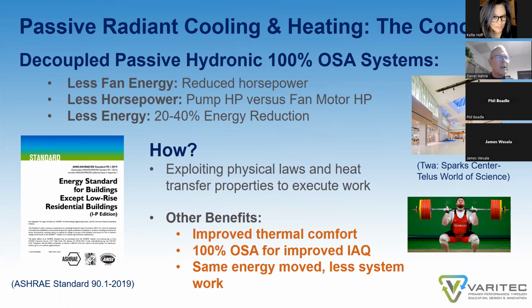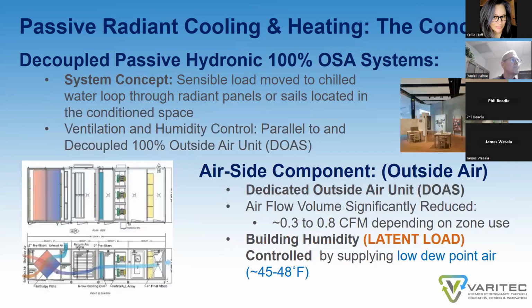There are other benefits other than the energy component as well. There's improved thermal comfort, which we're going to explore. 100% outside air systems have been known to provide better IAQ, and the same amount of energy can be moved from a building with less work. So again, to review the system concept, a passive system works with the sensible load moved to a chilled water loop through radiant panels and sails located in the conditioned space.